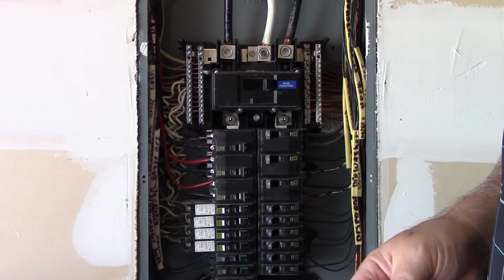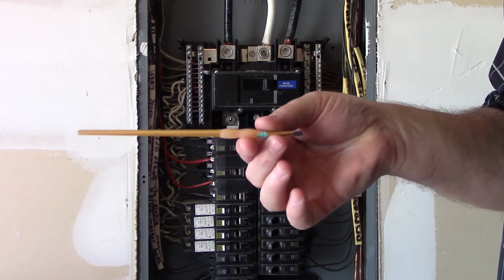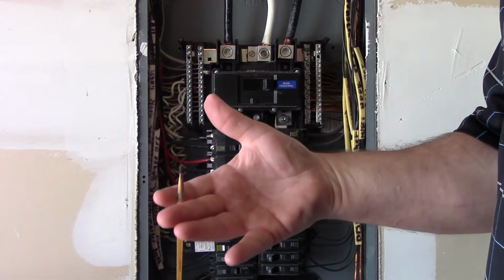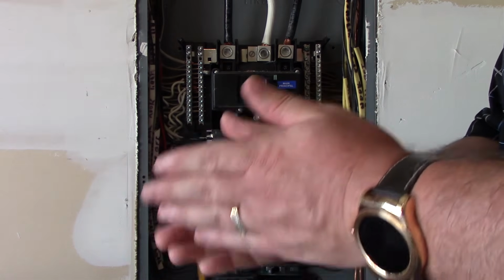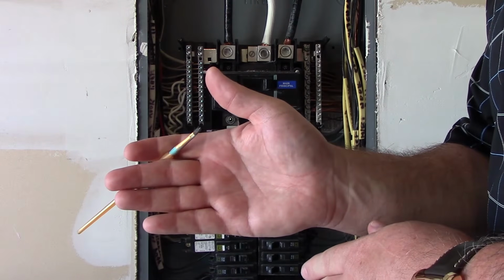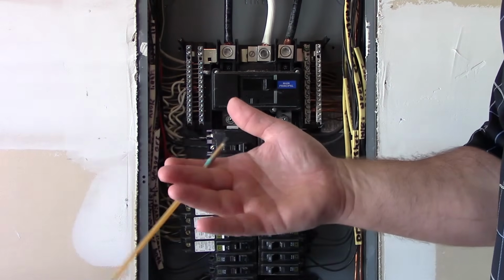Really too detailed for this type of video, but what you get is return current as 0 on the neutral. Okay, and it also carries the imbalance. So if I have 10 on one and 5 on the other, then I have 5 of imbalanced current that's actually traveling back on the neutral conductor.